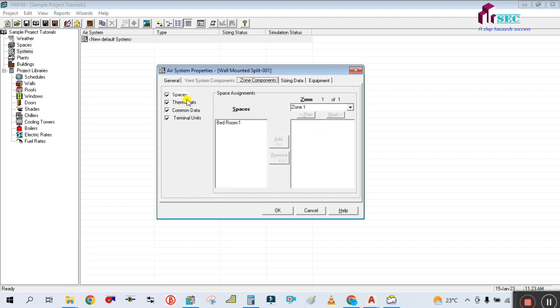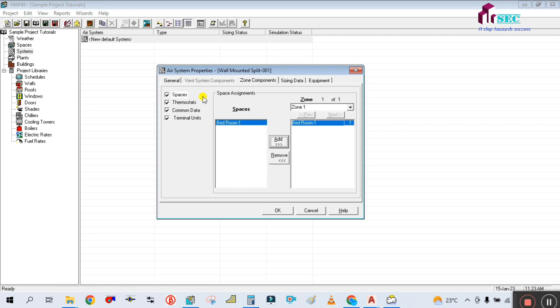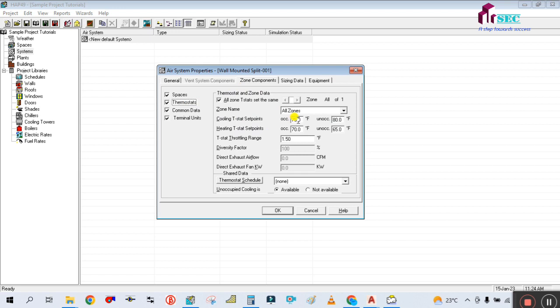Go to the Zone Component tab and select the space. Simply check this checkbox and you can see the space assignment. Bedroom One is added to the zone. Then go to the Thermostat settings. For the cooling thermostat set point, the set point is 24 degrees Celsius occupied, and unoccupied is 80 degrees Fahrenheit.